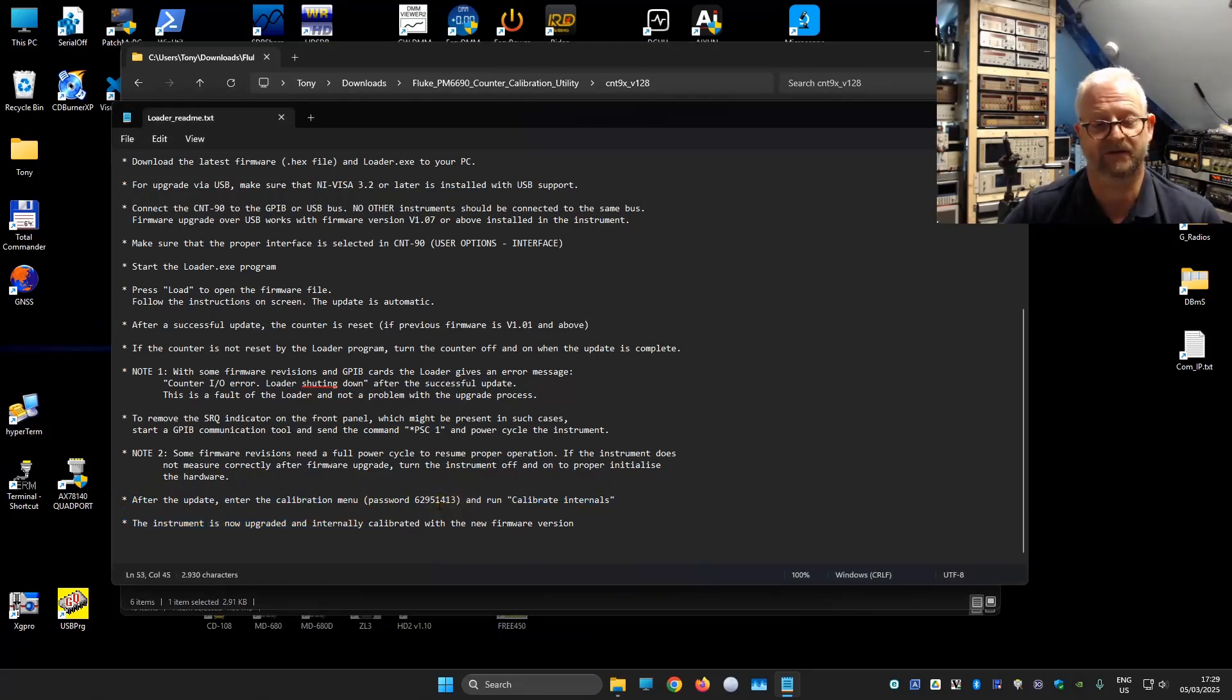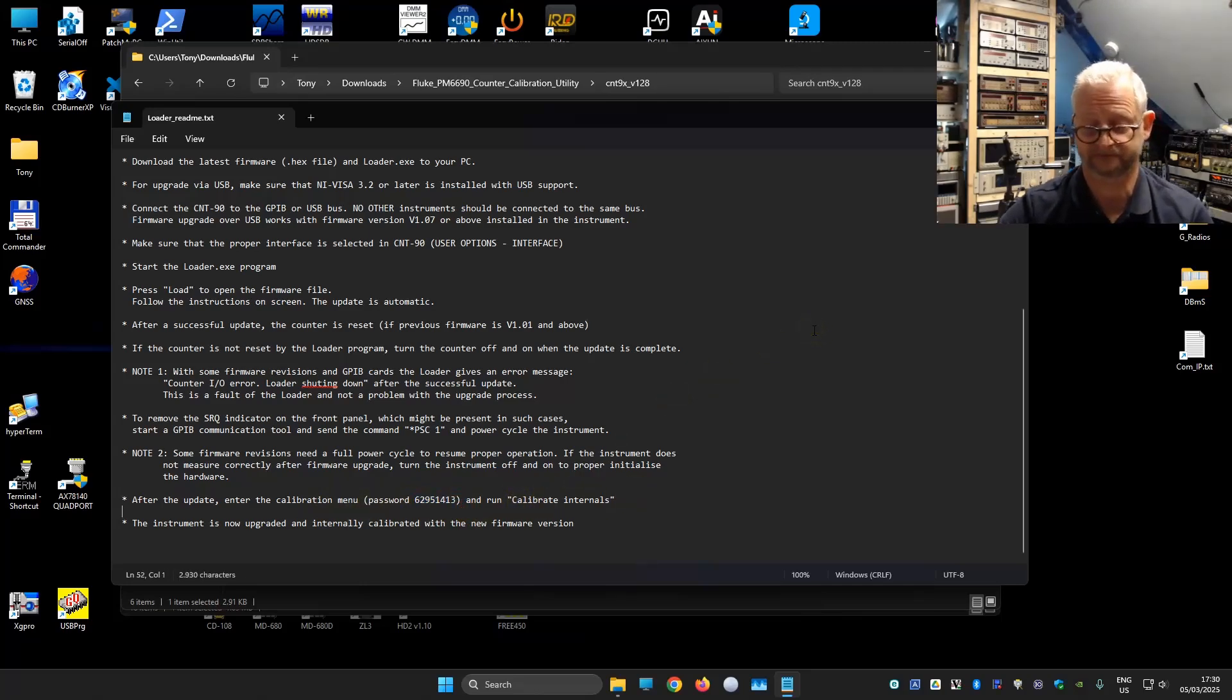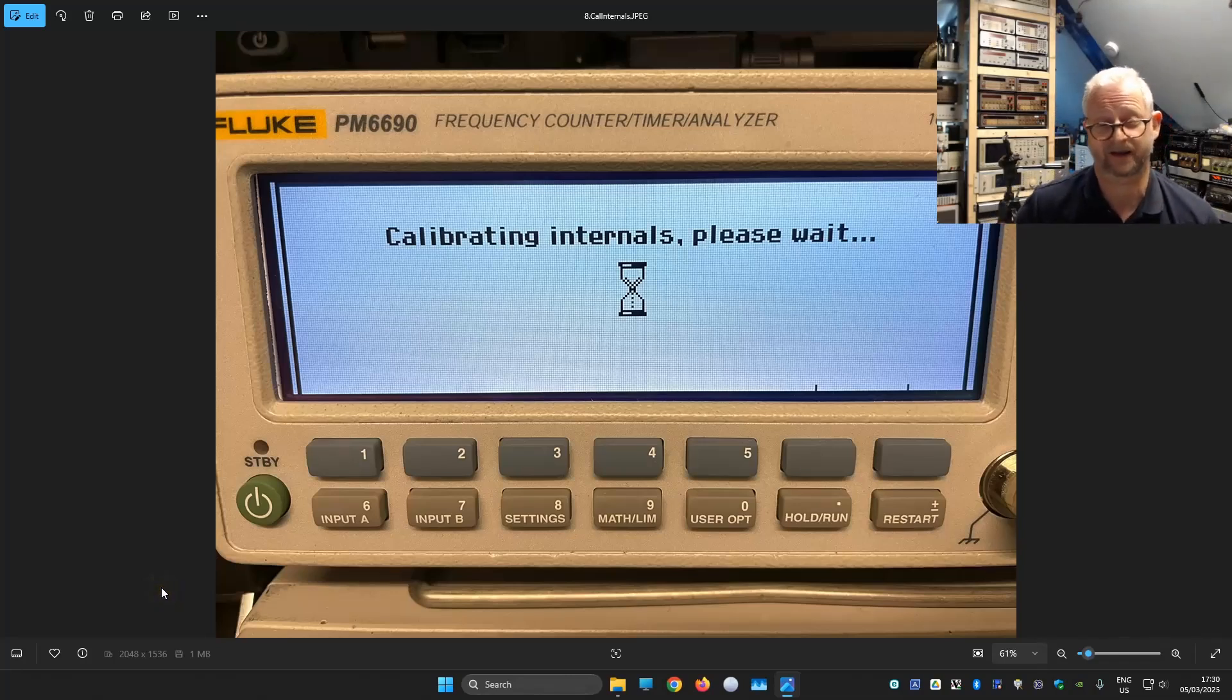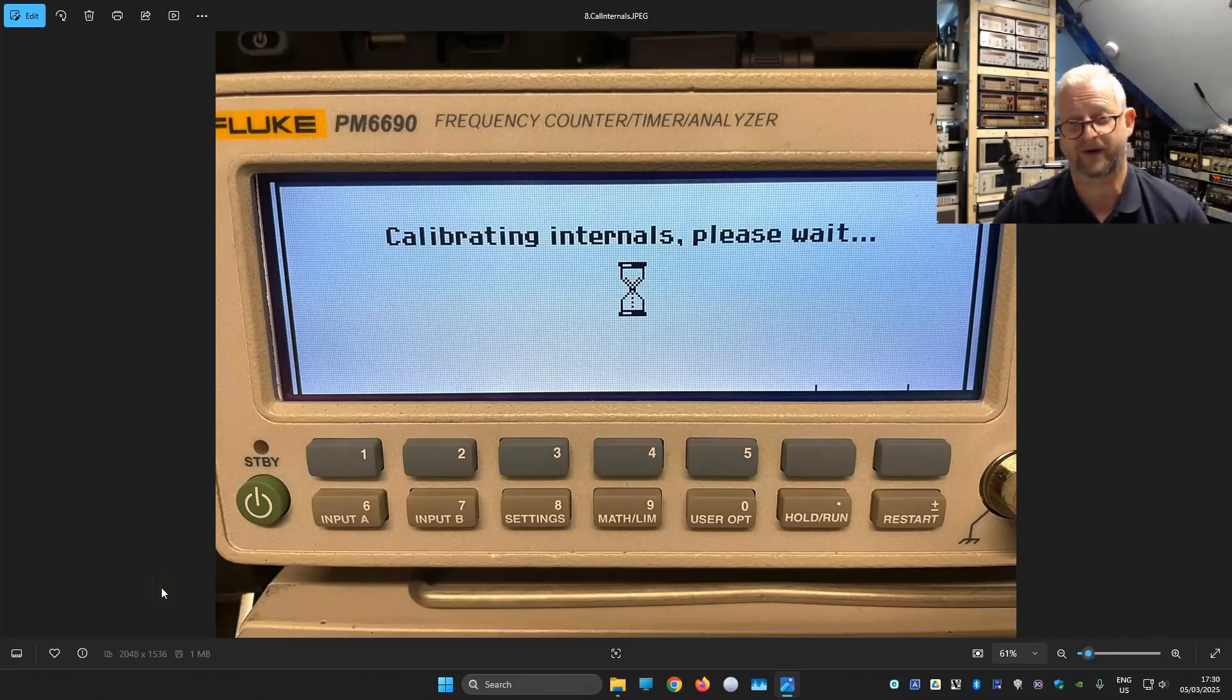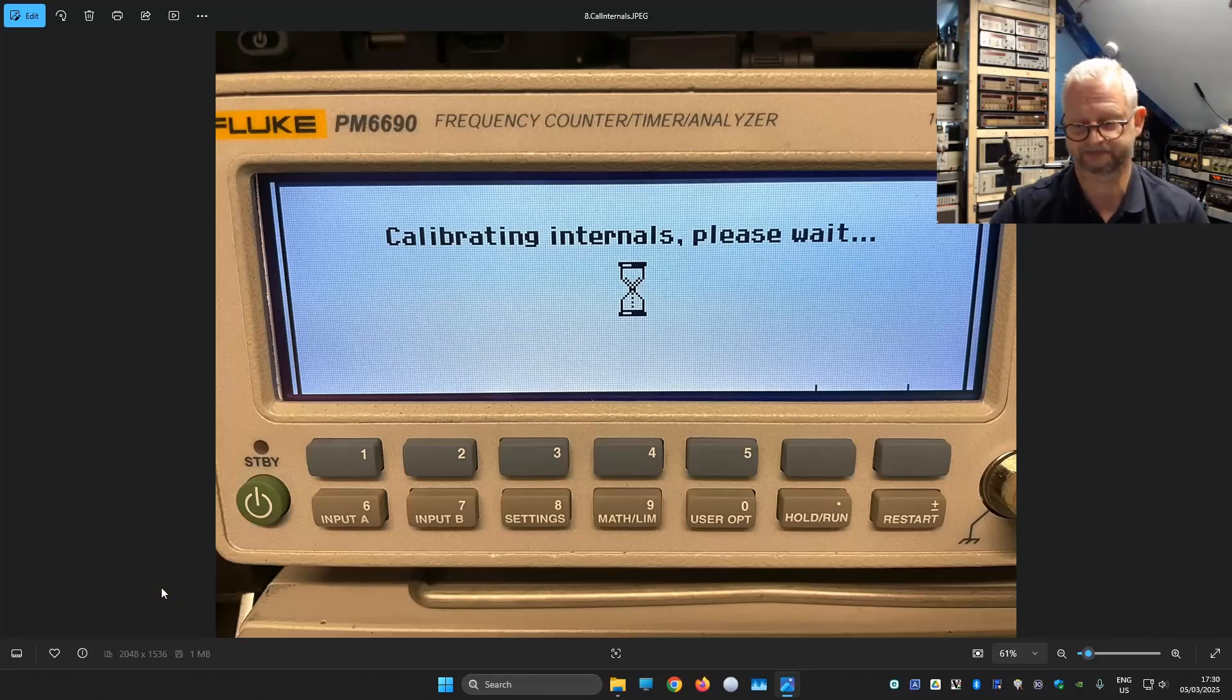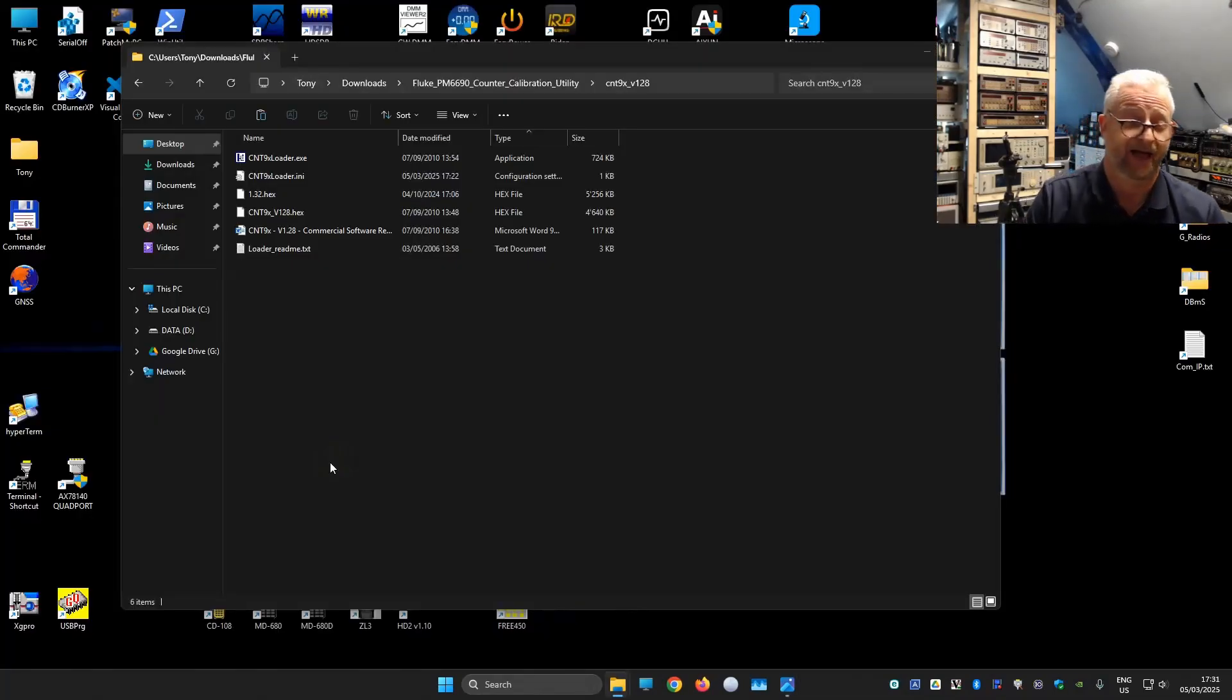You go to the menu, go to the calibration menu, you type this password here. And then you find an option calibrate internals. And then it looks like this. And this could take like three to five minutes. And just don't touch anything. Just wait until it's done. So that's it. It's actually quite simple.